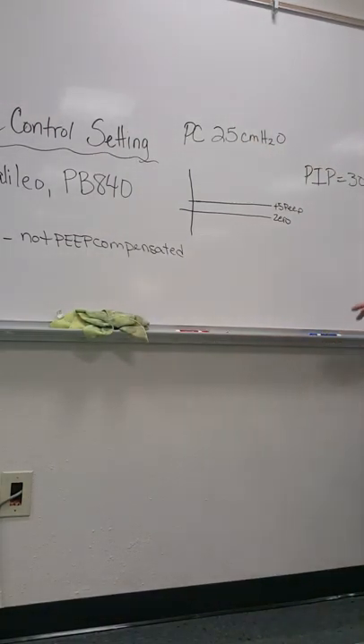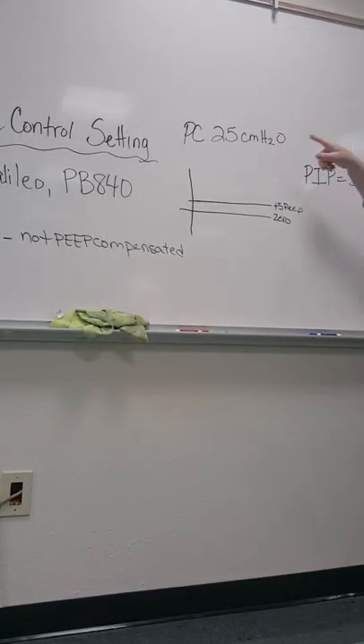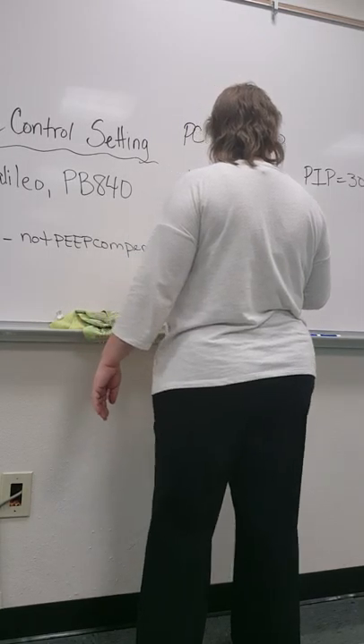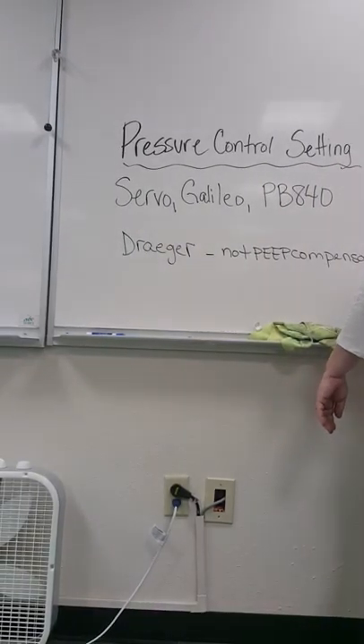Right. So in the Dräger's mind, if it really had a mind, the baseline on the Dräger is 0, even though you have 5 of PEEP set. So when you do the Dräger, you have to add the PEEP into the pressure control setting ordered by the doctor. So on the Dräger, the P-inspiratory pressure, because that's in our setting, has to equal 30.